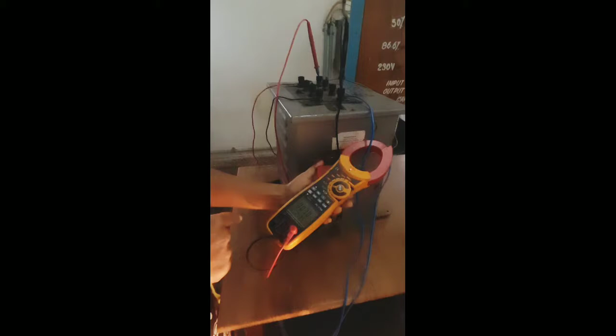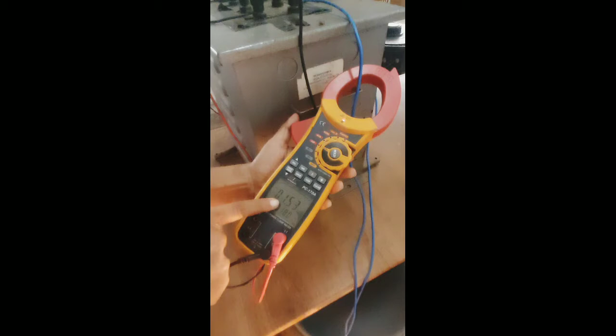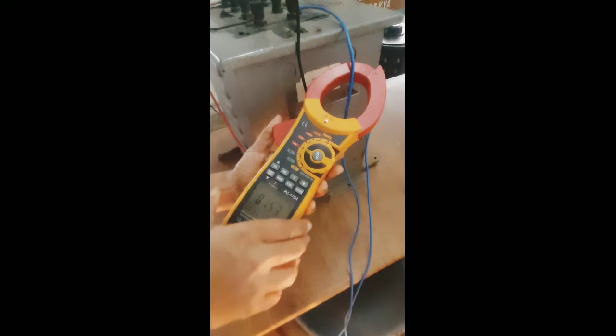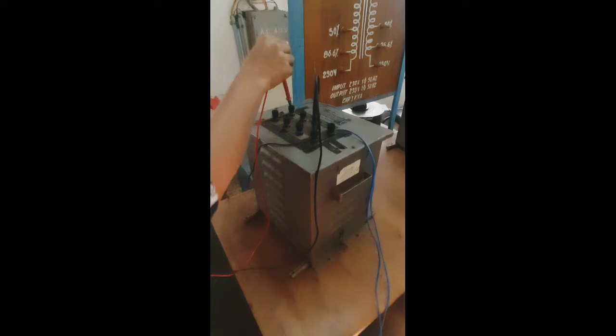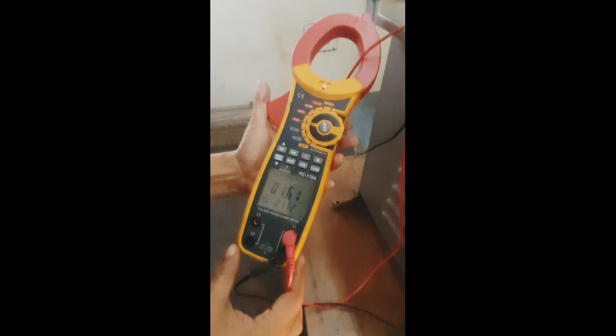Now in the secondary side the load is connected and half of the load is switched on. At that time we see the watt meter reading at the secondary. The value is 1.53 kilowatts at the secondary side. At the same condition, what is the power taken at the primary side? Here we connect to the primary, and the reading is 1.61 kilowatts. This is the second reading, taken at half load.